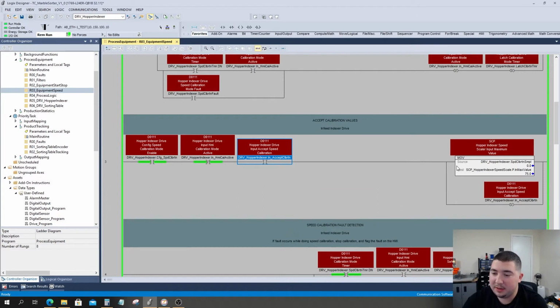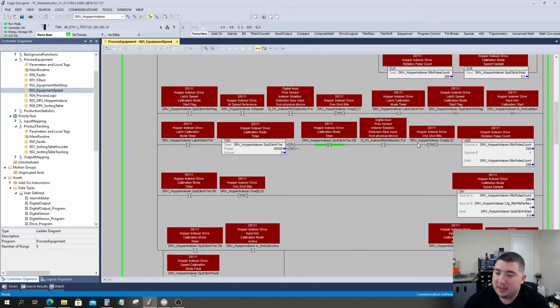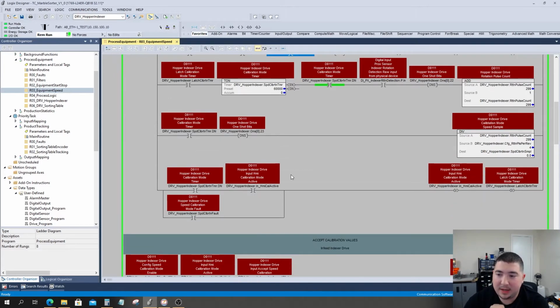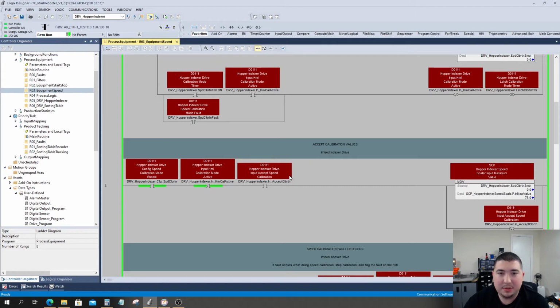So this one is for the indexer, but we also have the sorting table motor that we would want to calibrate. Now for the indexer, we've been using the rotation detection sensor. This is a good tool if you only have something like this as a means of input to know when the axis is rotating. However, with the sorting table, we actually have an encoder mounted on the back end of this device. So we can actually use that to our advantage.